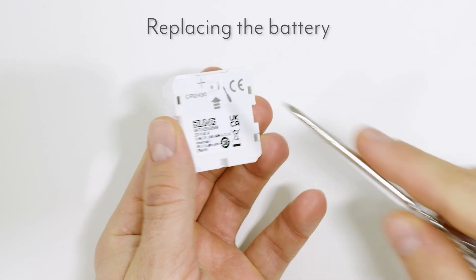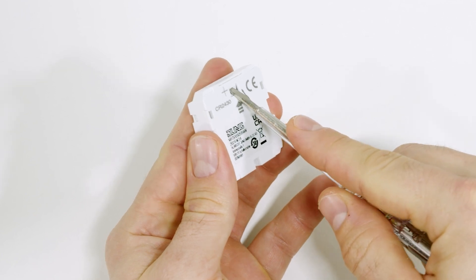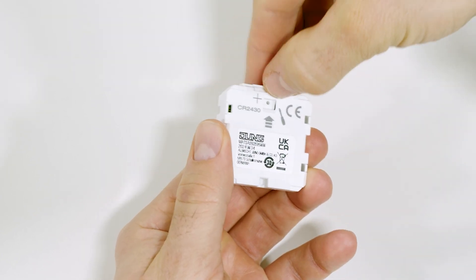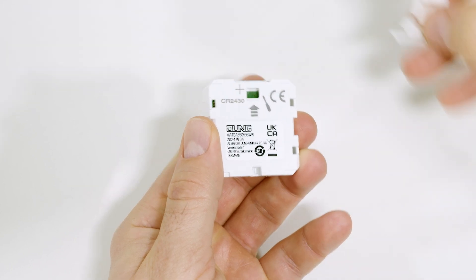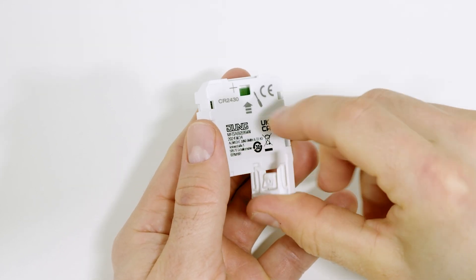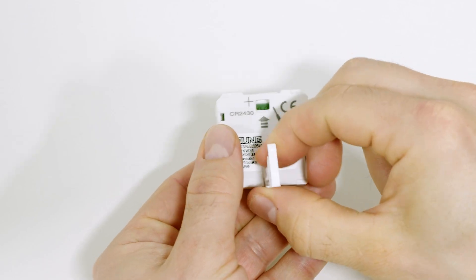Unlock the battery compartment cover by pressing on the tab on the back of the radio module with a flat blade screwdriver and sliding it forwards. Push the battery out using the battery compartment cover. Take care not to push the battery out with a screwdriver as this can lead to damage inside the module.